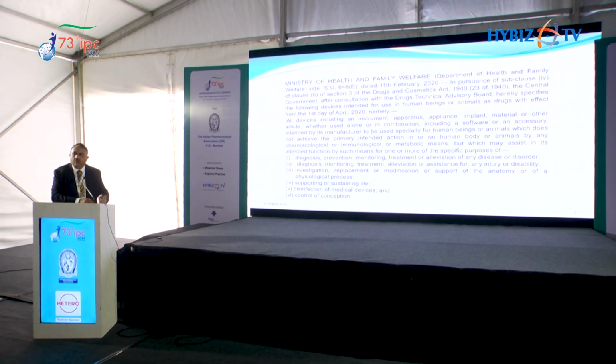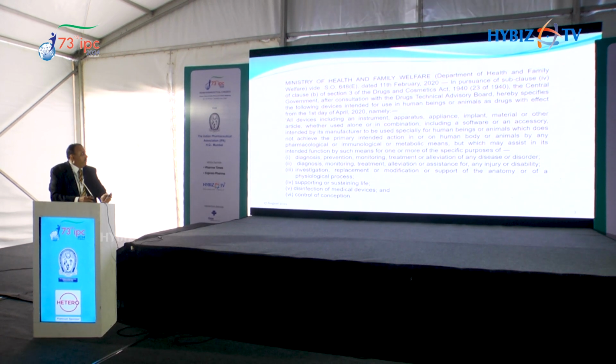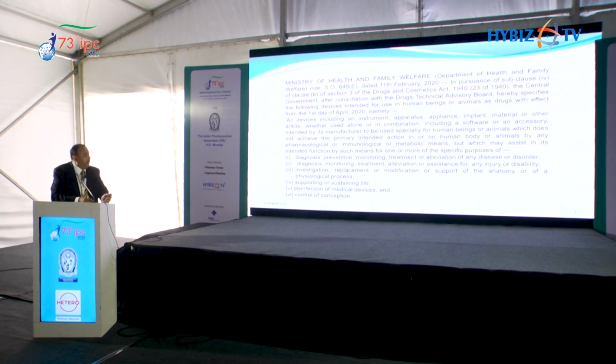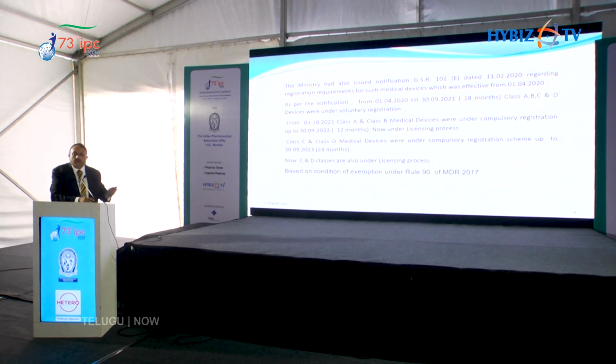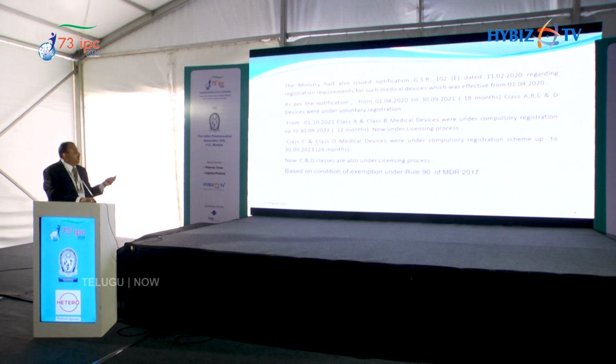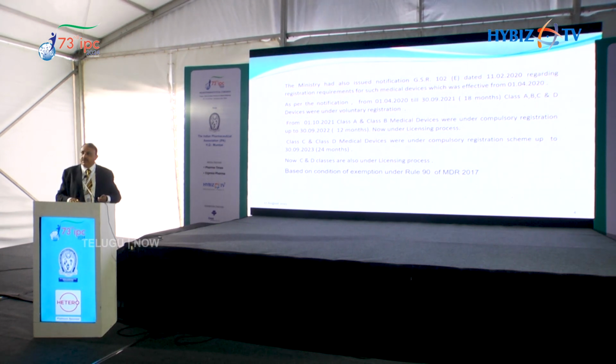This is the definition. Already Ramakrishna ji has told about the global definition of medical devices, and this is the definition under the medical device rules with effect from 1st day of April 2020, as per notification 648 dated 11th February 2020. On the same day, a separate notification was issued for the registration requirement of medical devices.